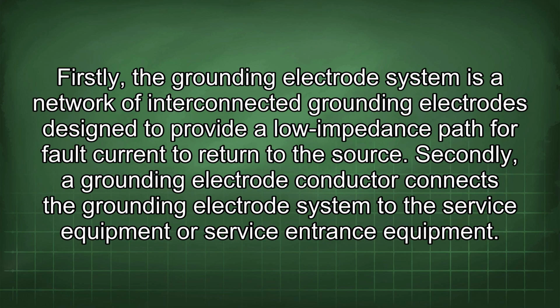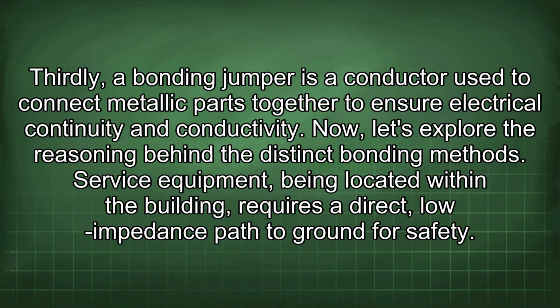Firstly, the grounding electrode system is a network of interconnected grounding electrodes designed to provide a low impedance path for fault current to return to the source. Secondly, a grounding electrode conductor connects the grounding electrode system to the service equipment or service entrance equipment. Thirdly, a bonding jumper is a conductor used to connect metallic parts together to ensure electrical continuity and conductivity. Now, let's explore the reasoning behind the distinct bonding methods.